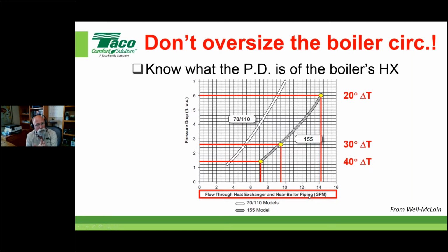So just remember, look and see what the manufacturer says. They'll normally say this is the heat exchanger only, or in this case, flow through the heat exchanger and near boiler piping is what this number here is. And you can do a comparative, like maybe I'll throw 3 or 4 different boiler brands out there, look at their 150,000 BTU model. Relatively speaking, they're kind of the same heat exchanger. And then you can look at the differences in pressure drop, and you can kind of tell which one's thrown some additional resistance on there for the near boiler piping and the ones that haven't.